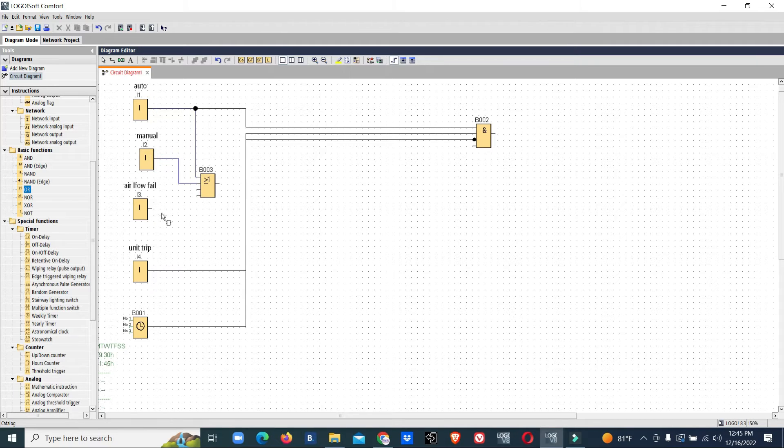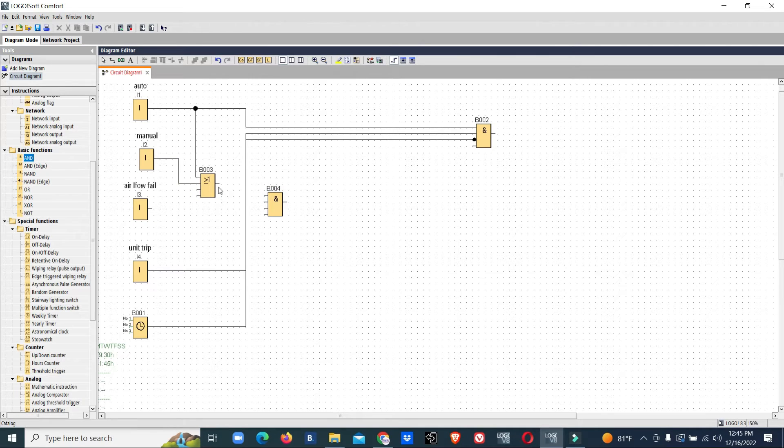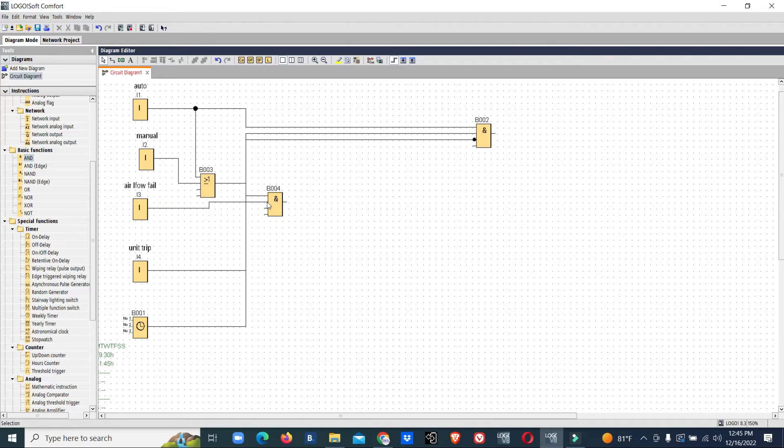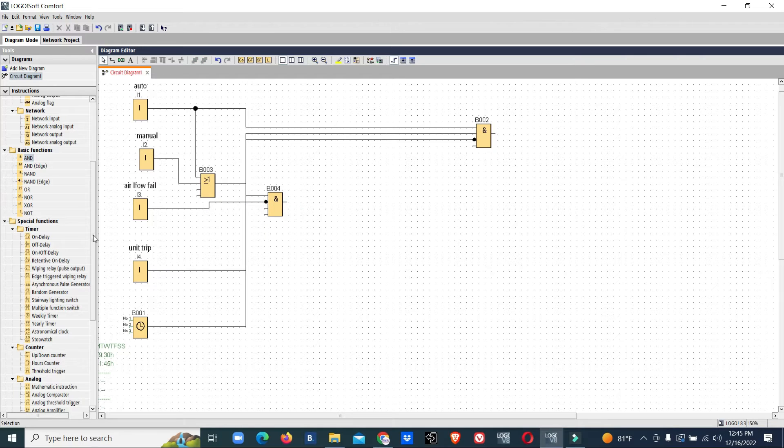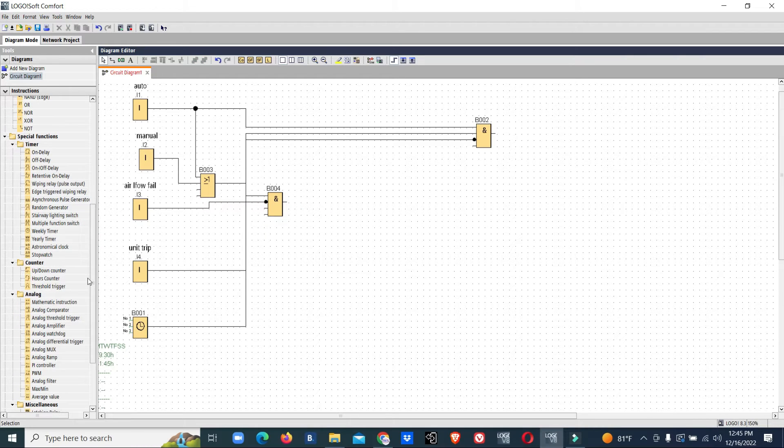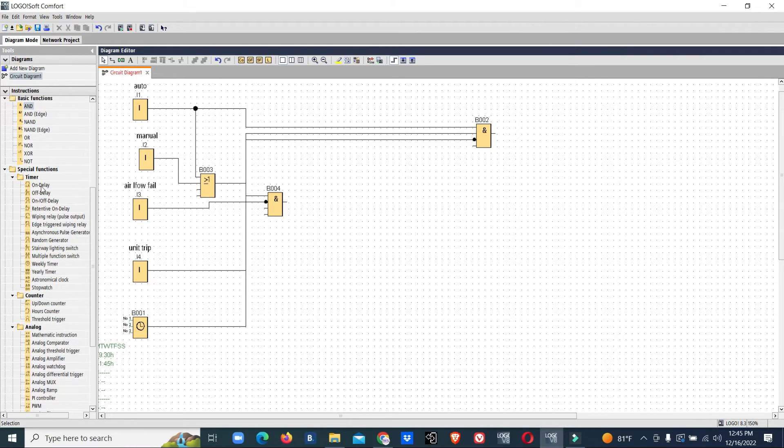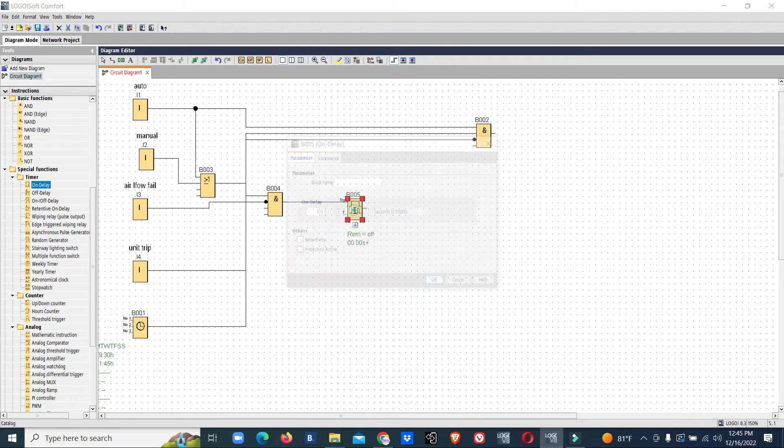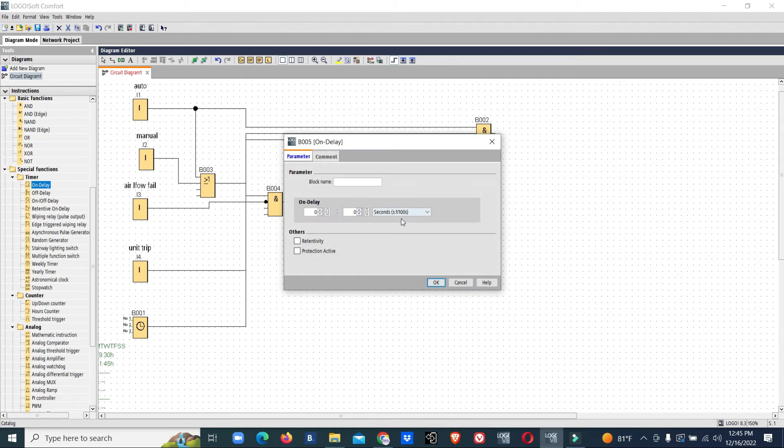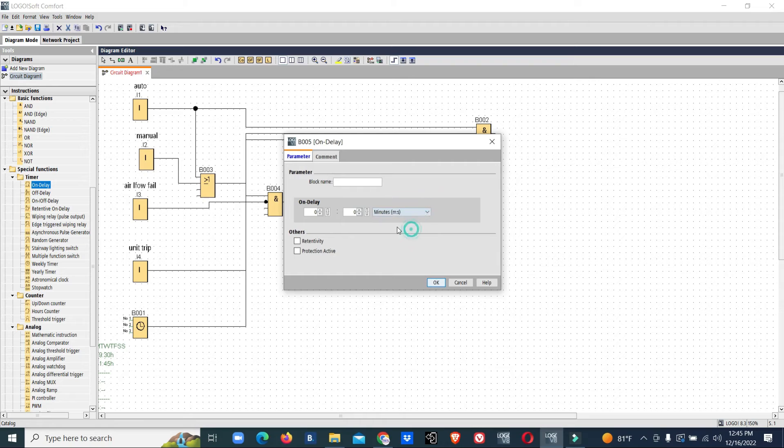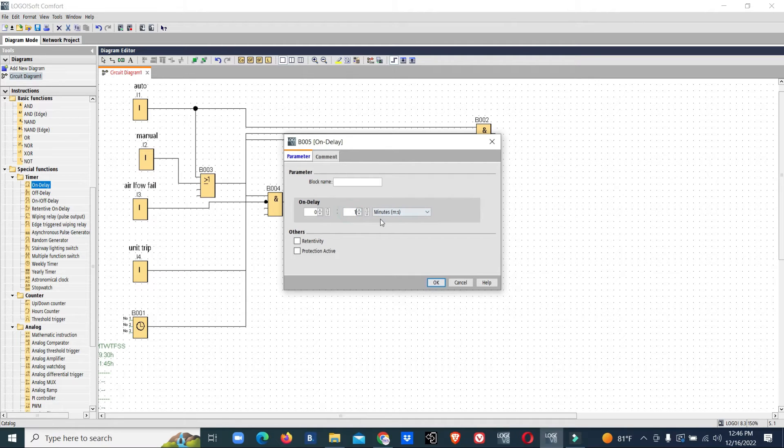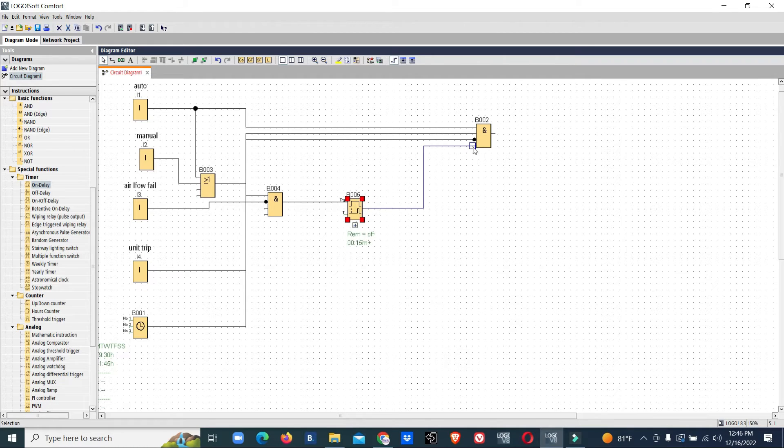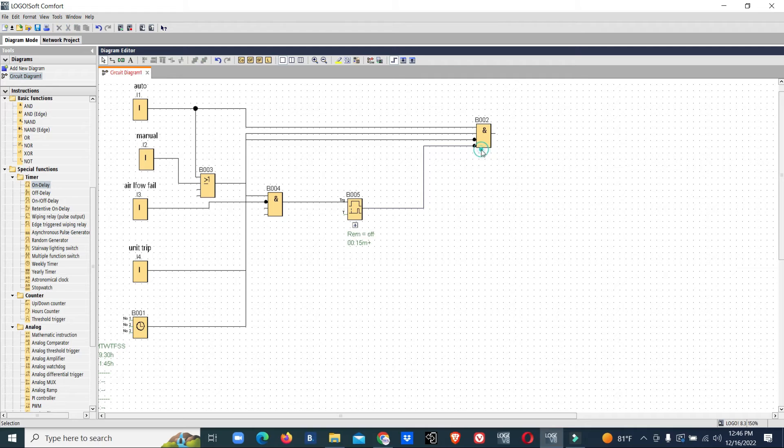We'll add an OR gate for auto and manual inputs, then add an AND gate. For airflow fail, we need to give NC—that means invert connect—then we'll add a time delay. We'll use an on-delay timer and set it to 15 seconds.